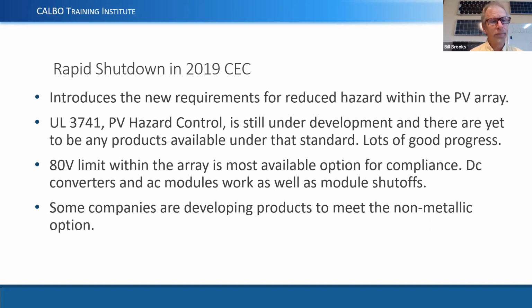Of course, the 80 volt limit has been around for several years as a requirement in California, ever since the beginning of 2019, or 2020 is when it actually went into effect in the 2019 California Electrical Code. So we can certainly use Enphase microinverters or other types of microinverters, SolarEdge optimizers, APC switches, AP system switches. There's a variety of switch technologies out there where we can turn the modules off at the module with these switches. Tigo, another example. So quite a few products on the market.